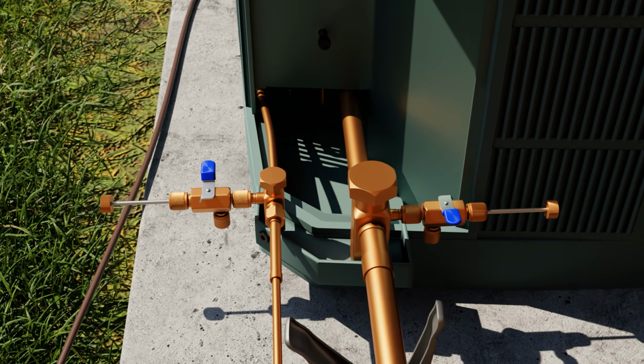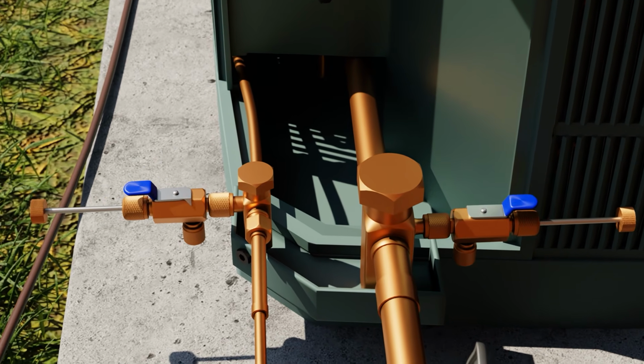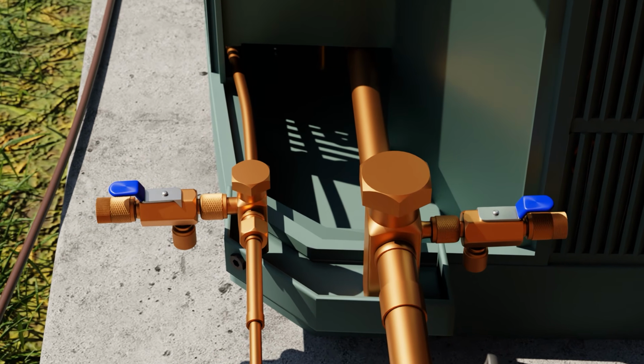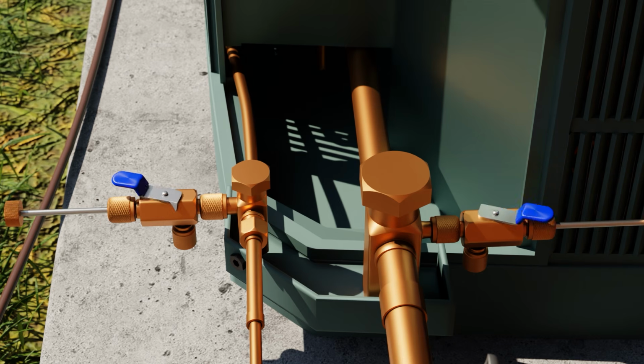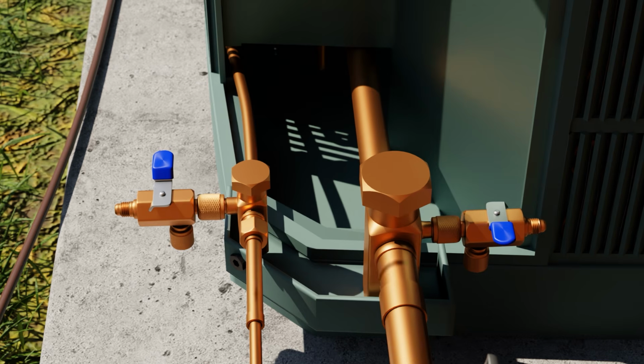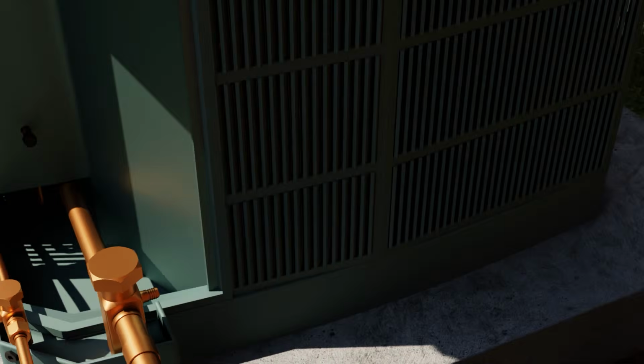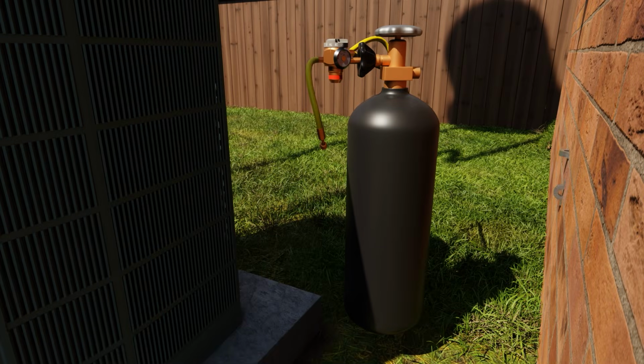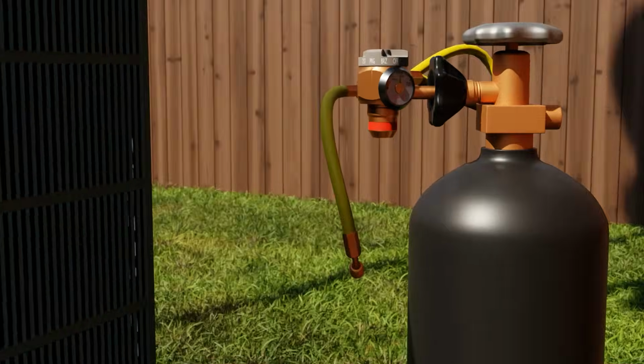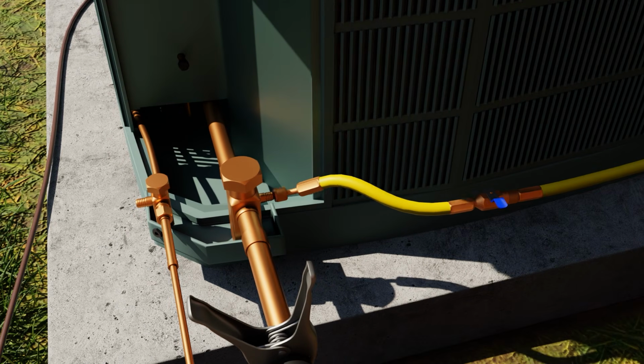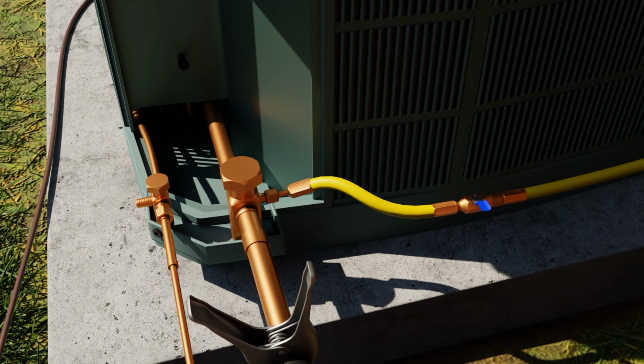Now we're showing this using the valve core remover tool, but you could use the one on the back of your screwdriver, whatever you want to use. But at this point, there's no refrigerant in the lines. It's all stored in the condenser, so it's safe to pull those cores out. Now we're going to prepare the system to flow nitrogen while we braze. As you can see, we attached the suction line, which means it's going to flow in the opposite direction through the evaporator coil and back to the liquid line.